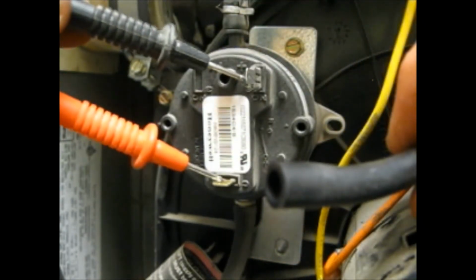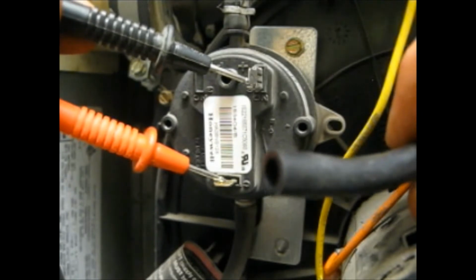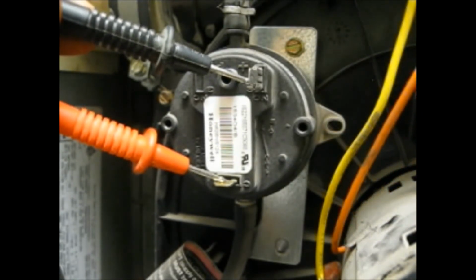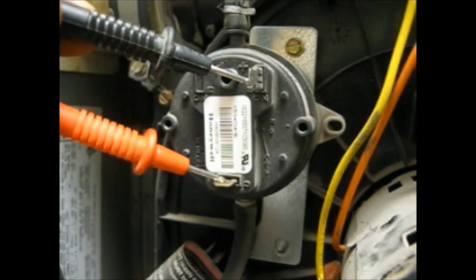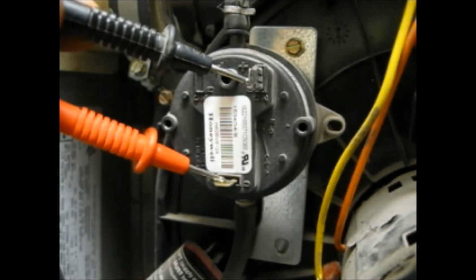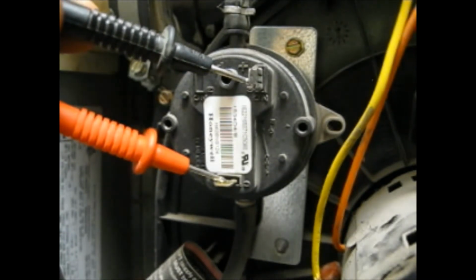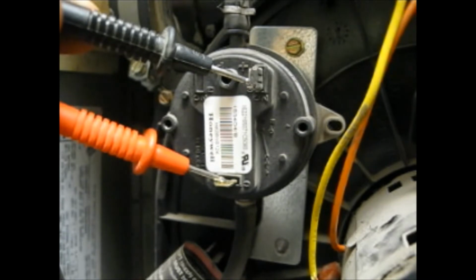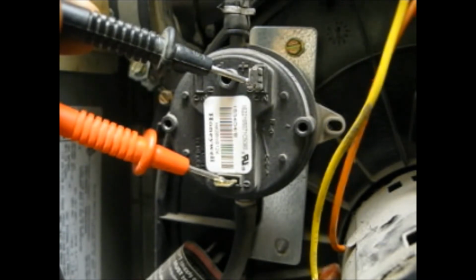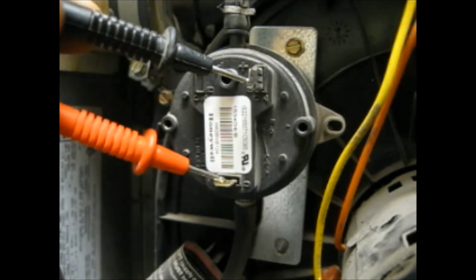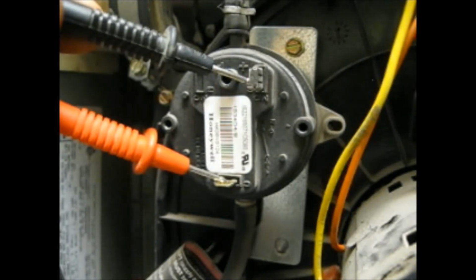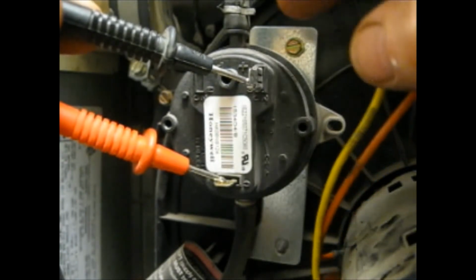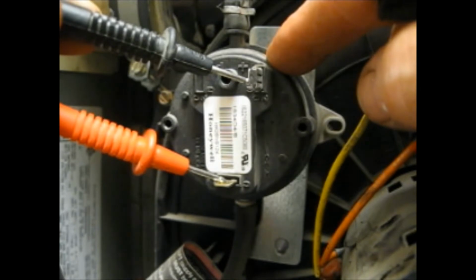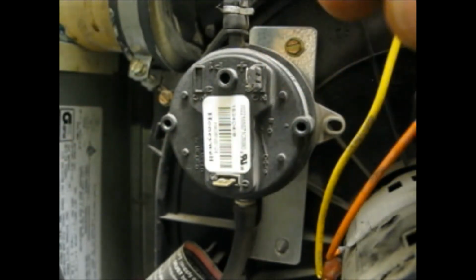So you're going to get your contacts from your ohm meter, put it on the pressure switch, and blow lightly. You can hear the contacts and the tone from your ohm meter that this is working. So this tells me that this pressure switch is working as it should. Go ahead and reconnect the hose and reconnect the contacts.